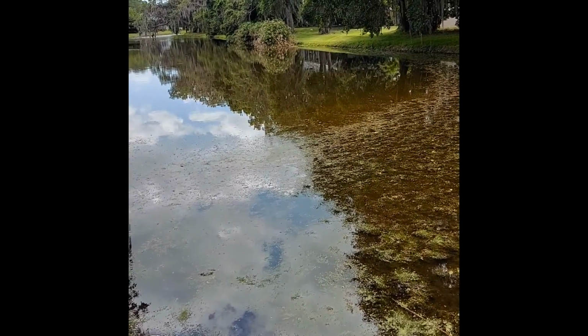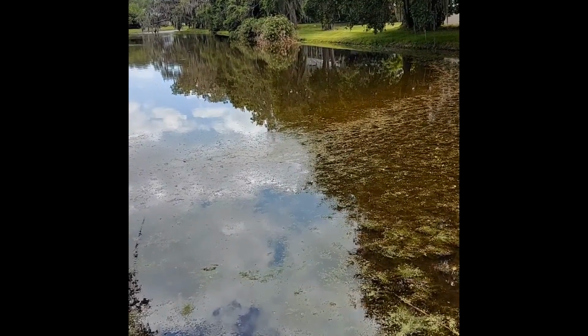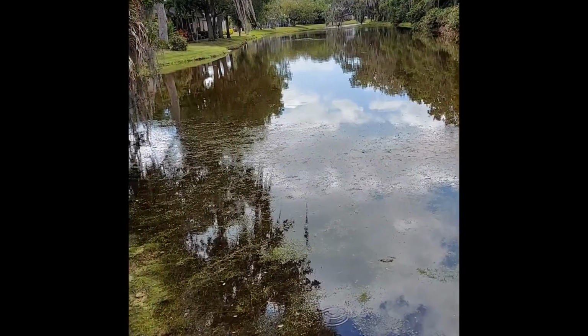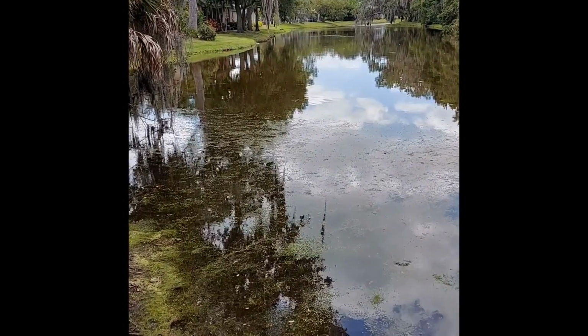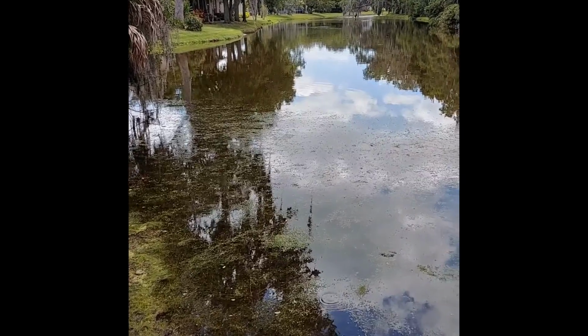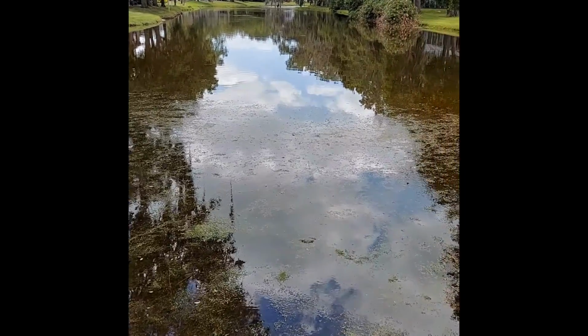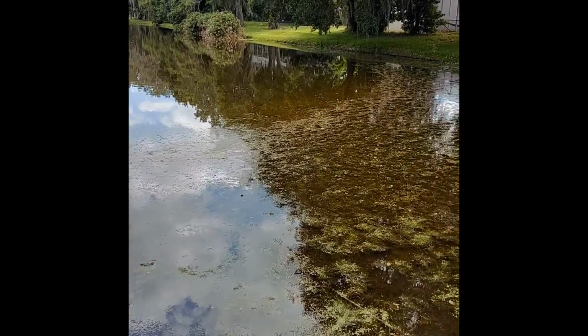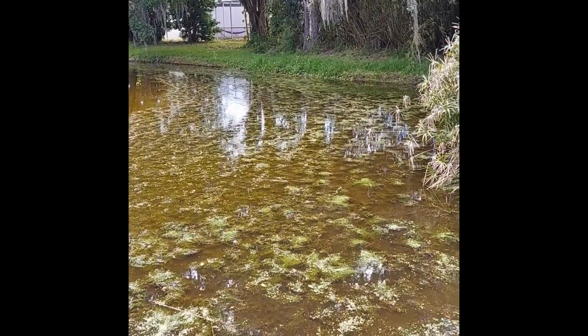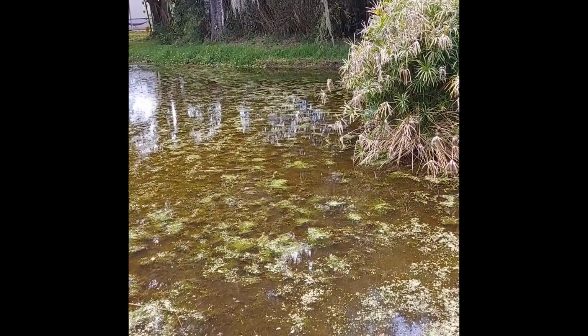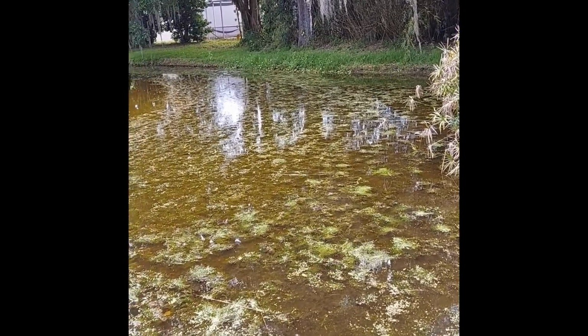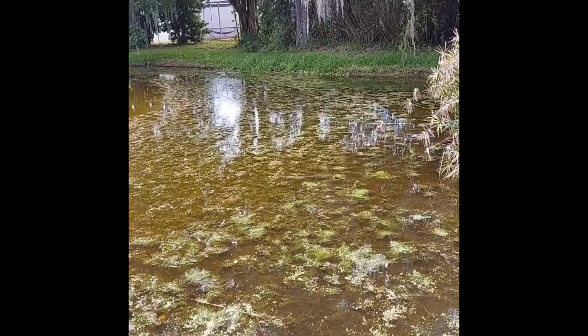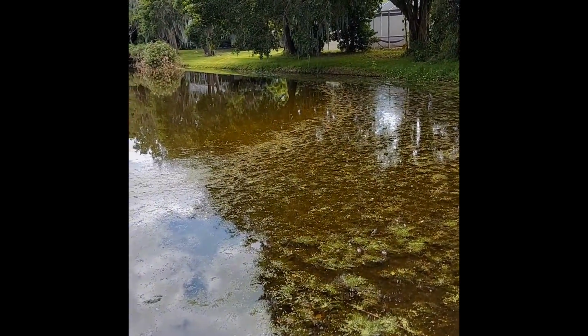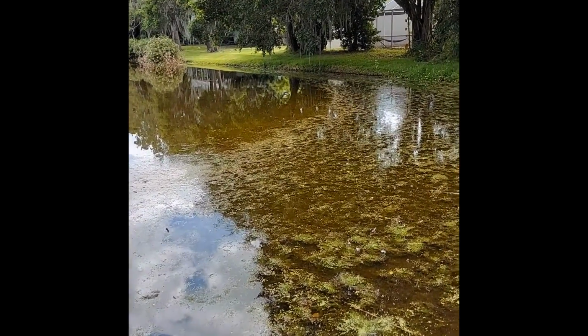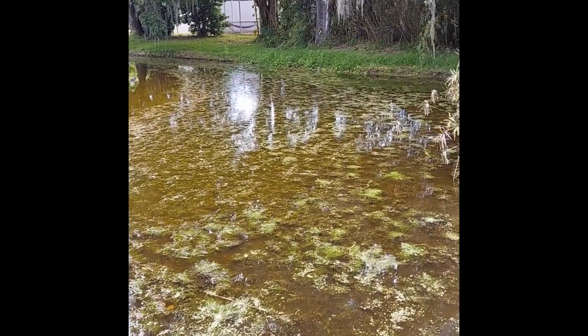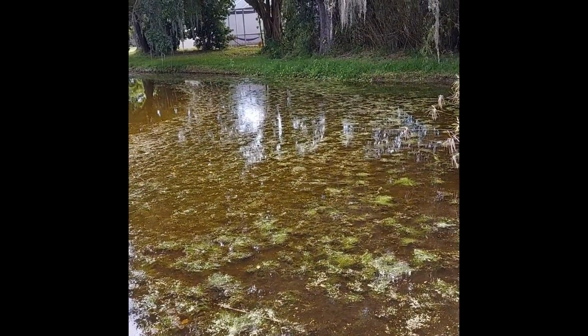And that exceeded the capacity of the pump to pump. So what I'm endeavoring to do is change that from a shallow well pump to a deep well jet pump of equivalent horsepower. The old pump was 1 horsepower, a Gould — nice pump, works great, just can't pull the water. It's about 125 feet from the pickup to where the pump head used to be. So we're going to replace it with a deep well pump and see what happens.